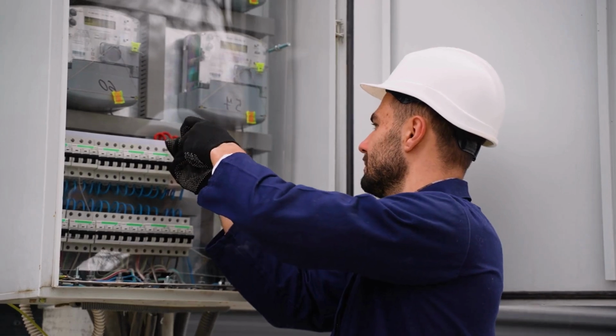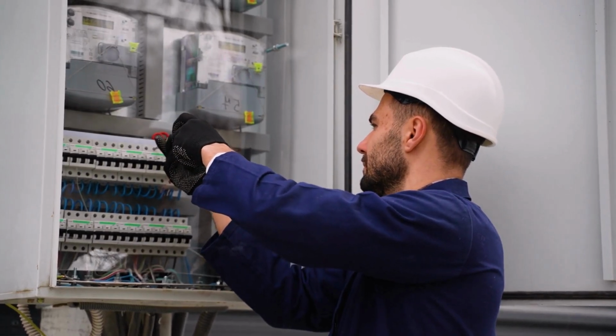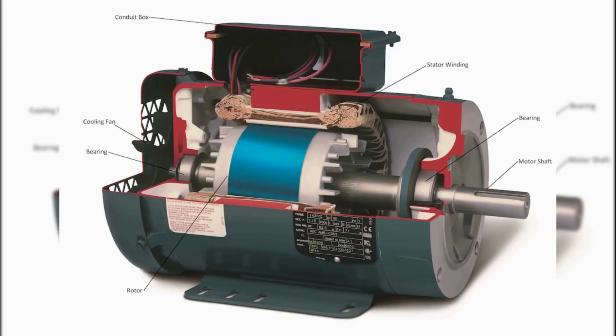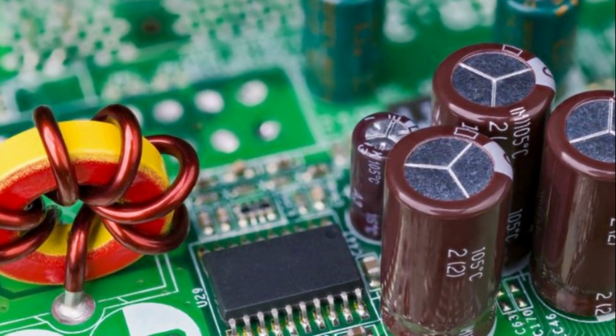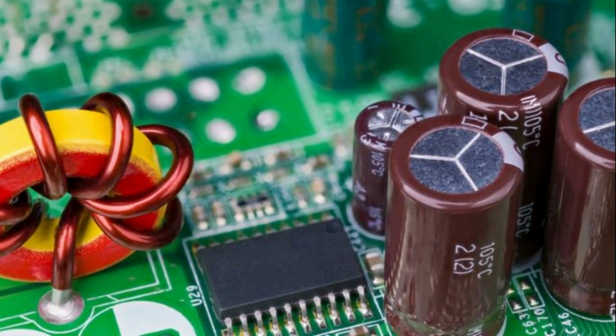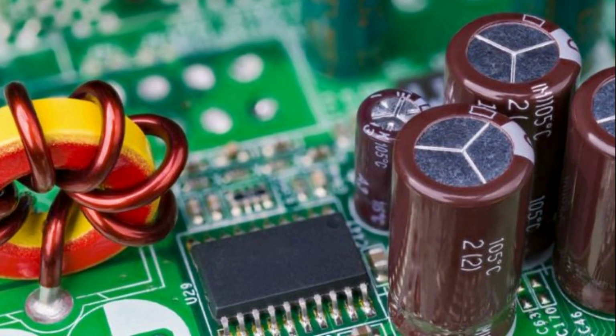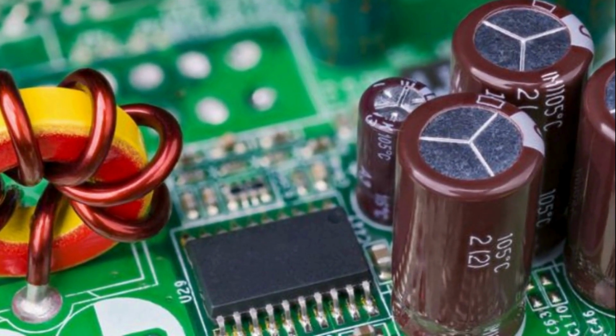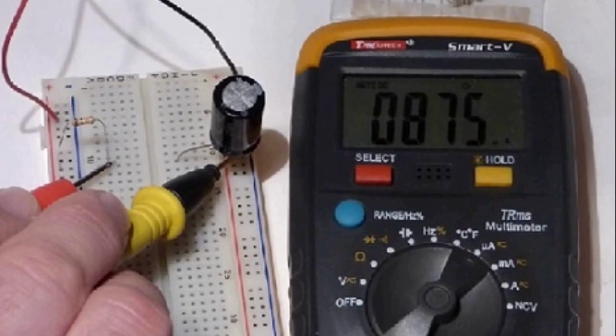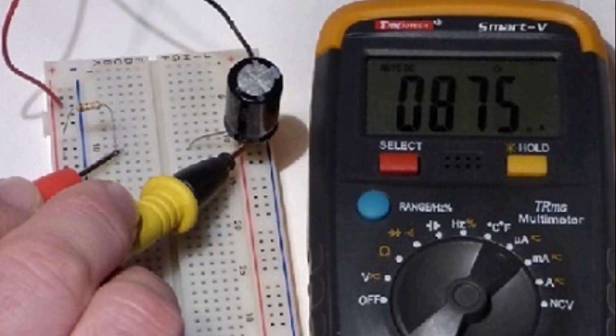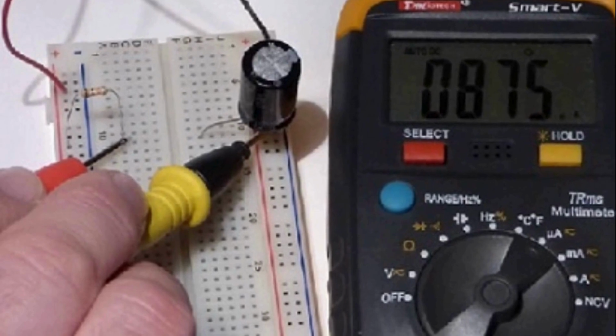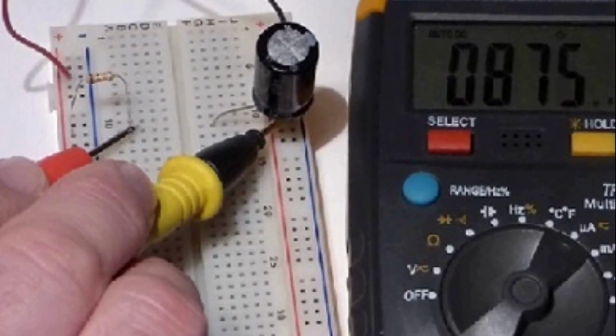Let's talk about where these hazards hide because they're not always obvious. Motor drives and variable frequency drives are probably the most common culprits. These devices use large capacitors to smooth out DC voltage for controlling motors. When you shut down the drive, those capacitors stay charged. Some drives have built-in discharge resistors that bleed off the energy over time, but not all of them do. And even the ones that have them can fail, leaving you with a fully charged capacitor bank that your meter won't detect from the input side.